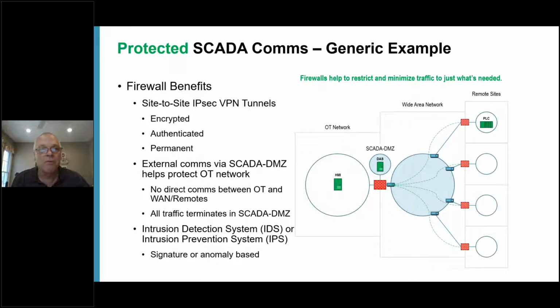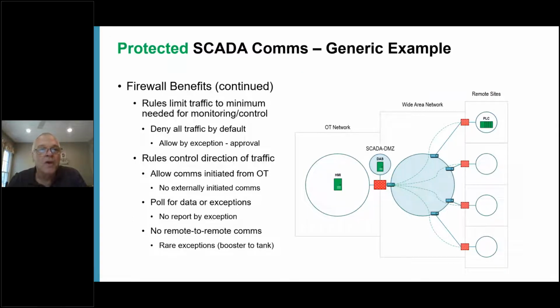So this is what we would consider a protected SCADA communication system, with the addition of these firewalls and the addition of that SCADA DMZ. We've got even more. If we use firewalls, we can use rules to limit traffic to the minimum needed for monitoring and control.